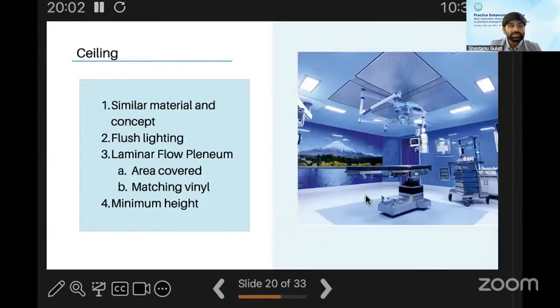Now the OT ceilings, with respect to the surface, follow the same concept. What is very important here is the laminar flow plenum. This is the stainless steel plenum that is shown above the operation theatre table, from which the filtered air of the AHU comes directly onto the operation theatre in a laminar fashion. What is important is the size. It has to cover the patient's head up to the torso.